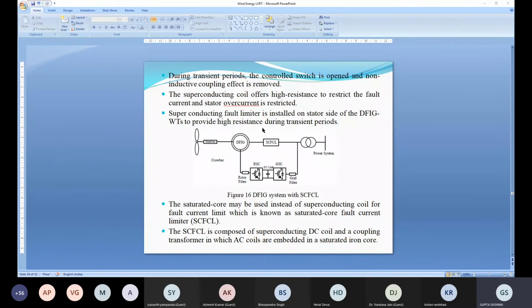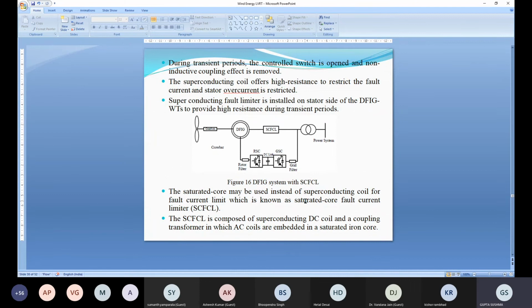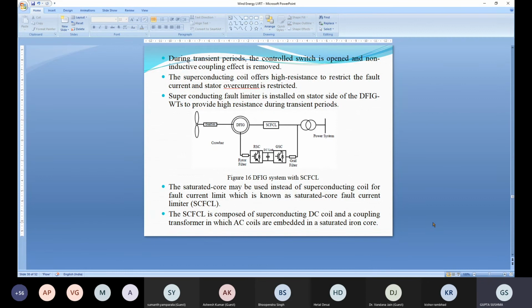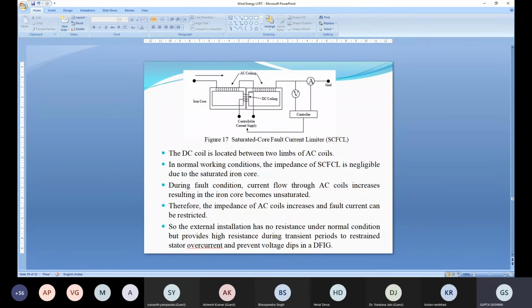Instead of this superconducting fault current limiter, we can use a saturated core also, a saturated core with superconducting coil. So a saturated core may be used instead of the superconducting coil. This is the saturated core fault current limiter.